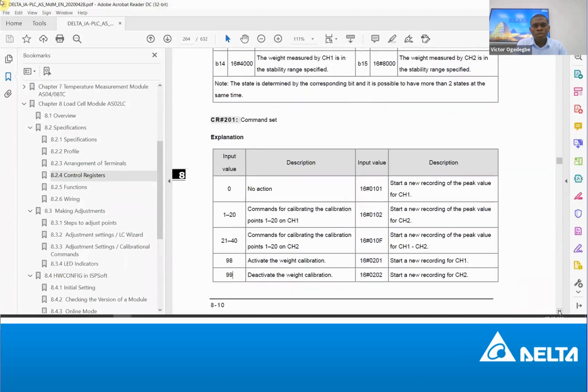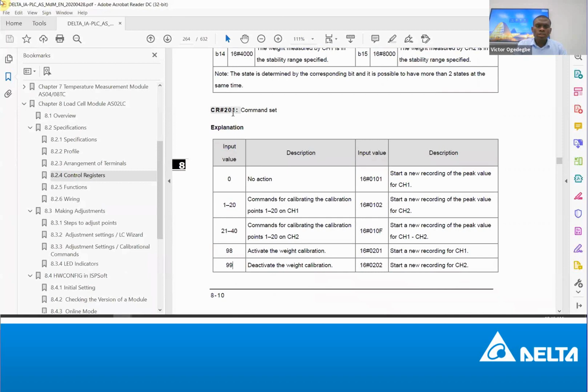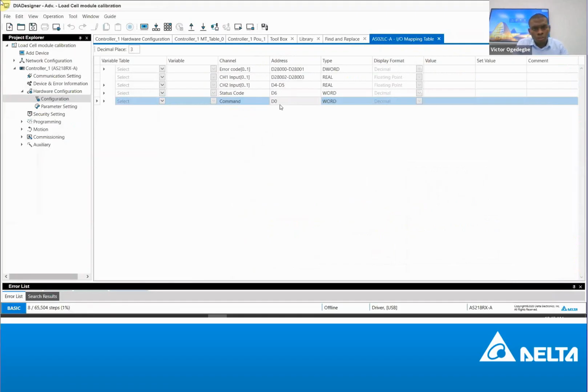Yeah, this is command set. So this register, control register 201. If you want to use the TO and FROM instruction to configure the module, you write it to this address. But in the case of our software, it has already just assigned D0. So anything I write in D0, it's like data exchange. It goes automatically to this register.